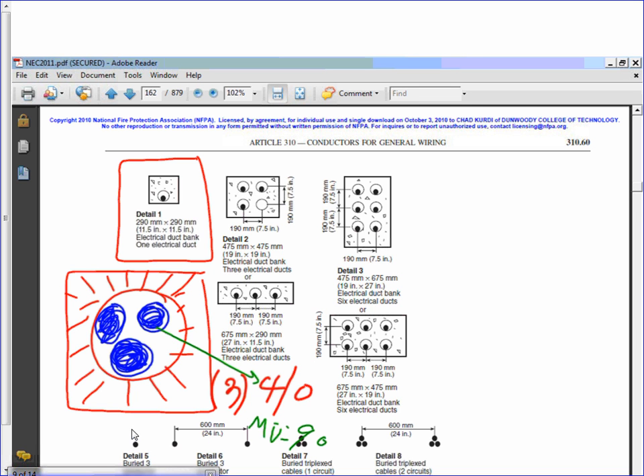Detail 1. This is how it looks. It's basically 11.5 by 11.5 inch. Imagine a cube of concrete, 11.5 by 11.5. Right in the middle of it is a duct, PVC, Schedule 80, surrounded by that concrete, or any duct that they make, concrete ducts, is surrounded by concrete. And you're pulling all these medium voltage conductors inside it. Why would we do something like this in medium voltage? Do we have to do it this way? No. That's one way of doing it.